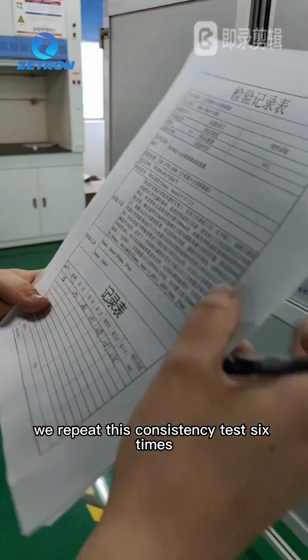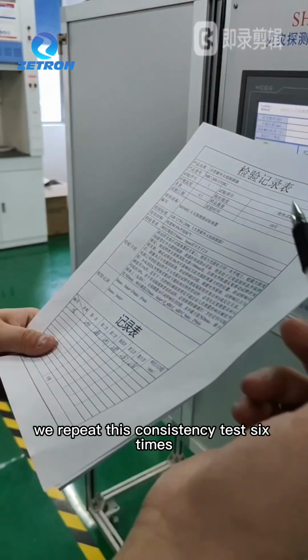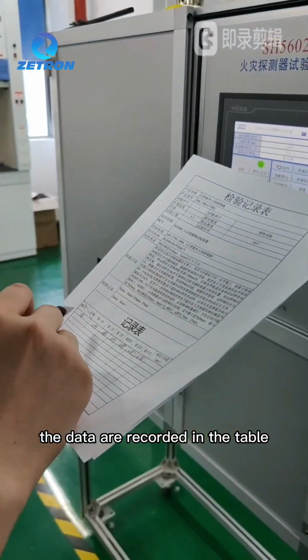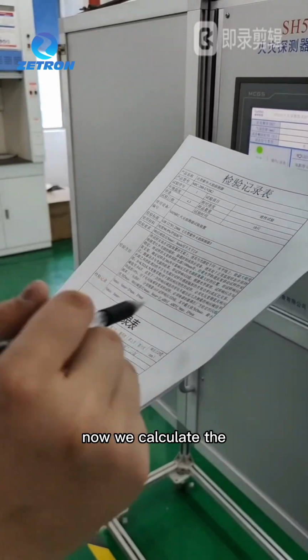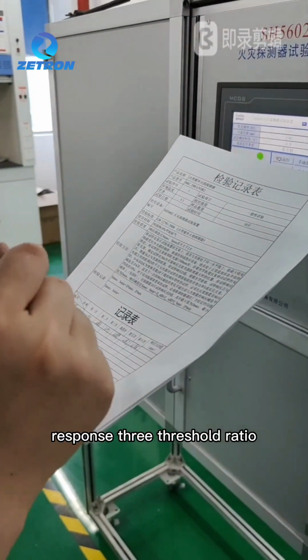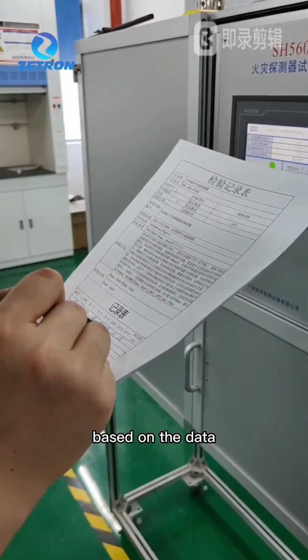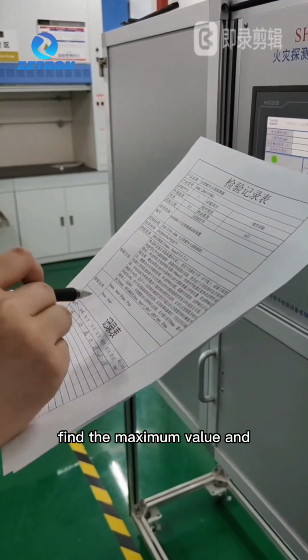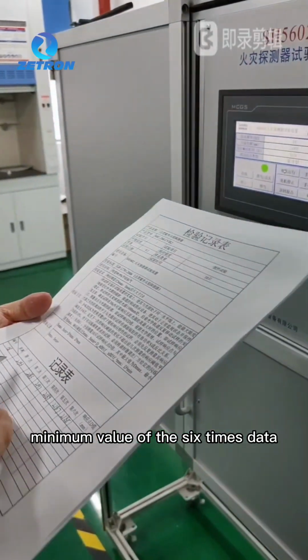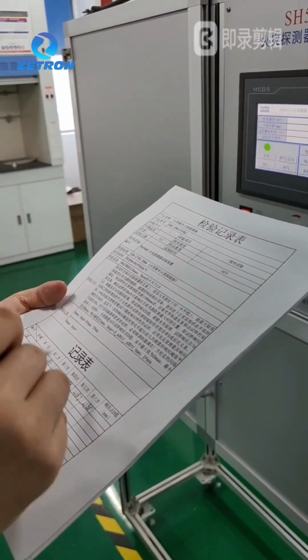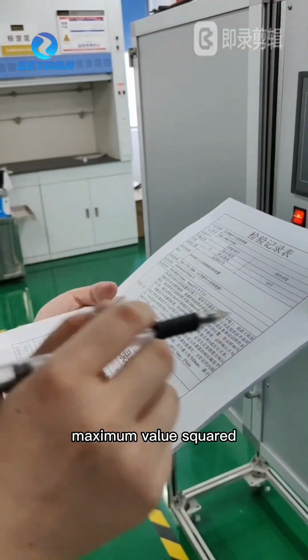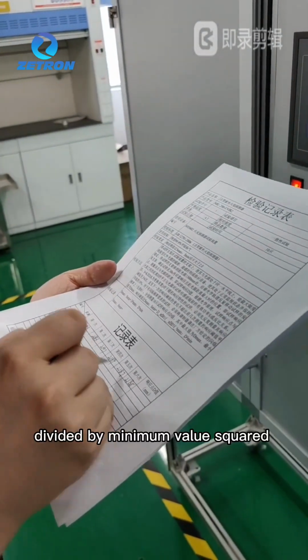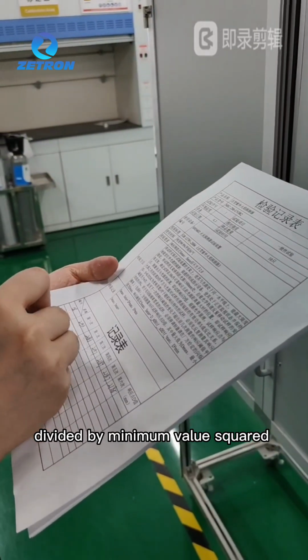We repeat this consistency test 6 times. The data are recorded in the table. Now we calculate the response threshold ratio based on the data. Find the maximum value and minimum value of the 6 measurements. According to the formula, the maximum value squared is divided by the minimum value squared.